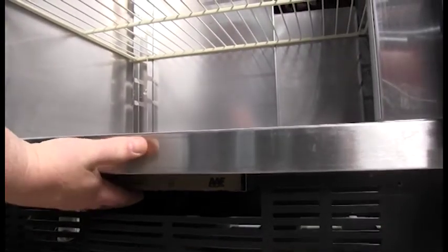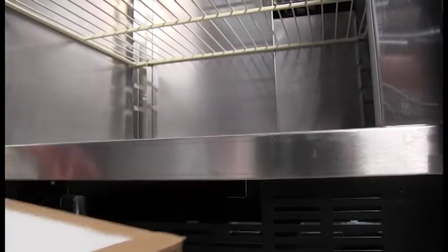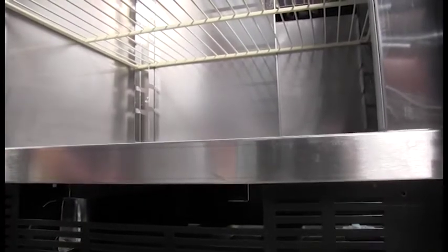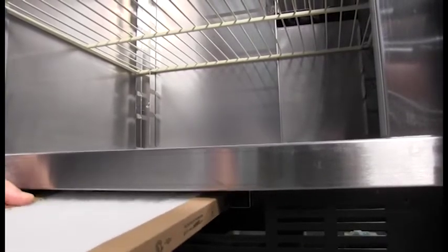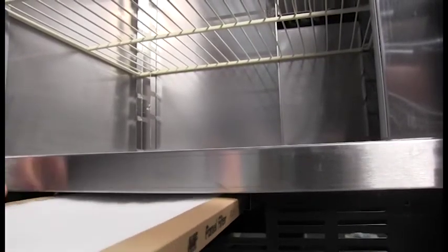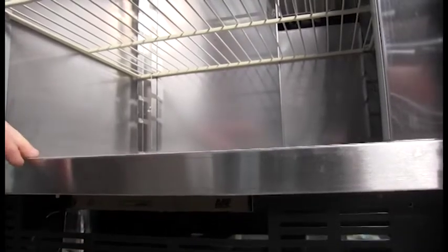Pull filter out from the lower left front corner of the unit. A filter may be used twice. If only half the filter has dirt on the surface, rotate the filter to use the other half. If both sides have been used, replace with a new standard 24 x 10 x 1 inch furnace filter.